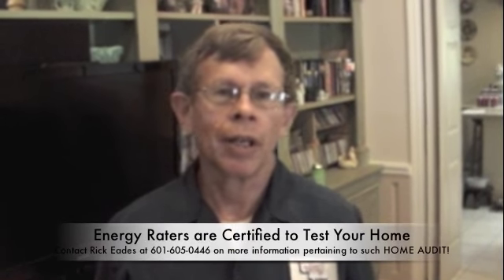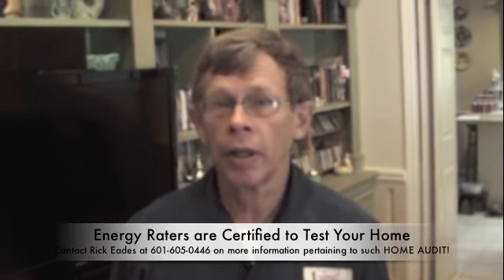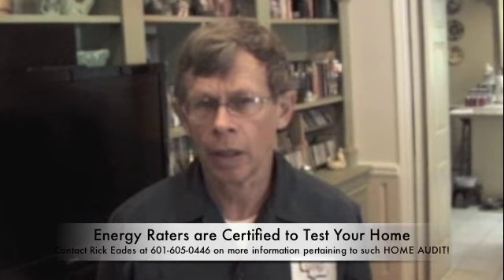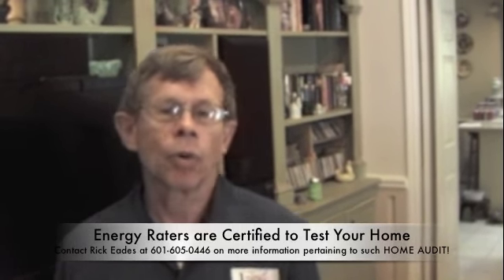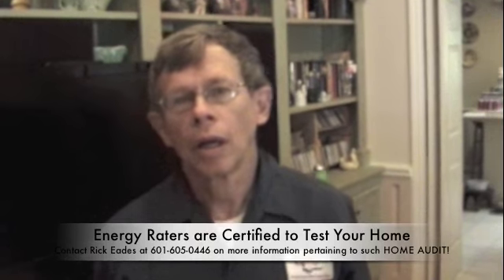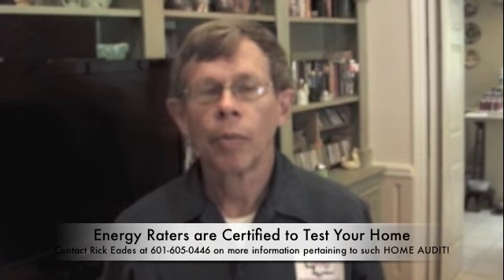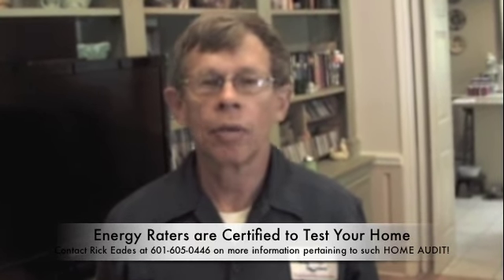And this is the energy savings you can predict even before making repairs. The tests were very easy to conduct. We have a fabricated door that we put in the front door of the house, and we depressurize the house. For the ductwork, we tape over the duct registers, the air diffusers, and then pressurize the ductwork, and from that we can measure any leakage. The leakage is a cost waste.